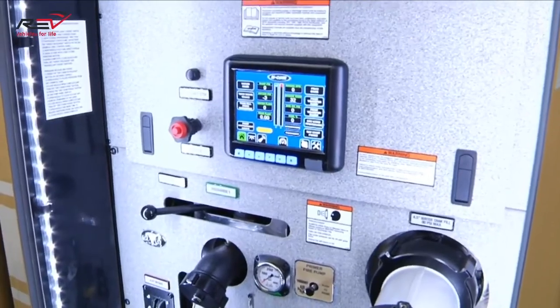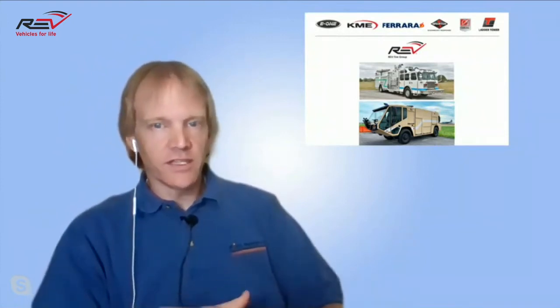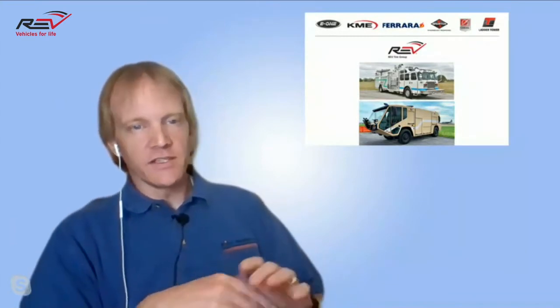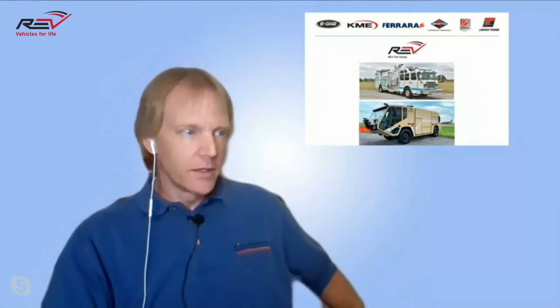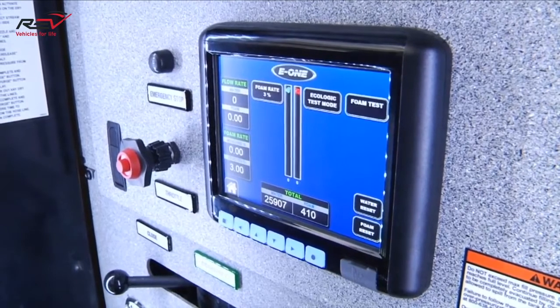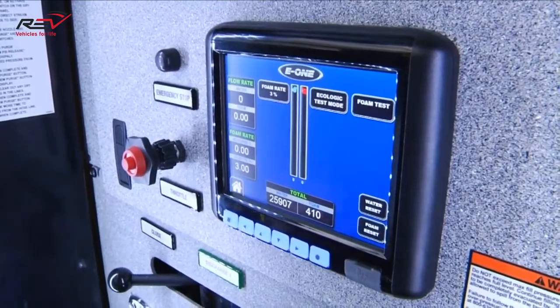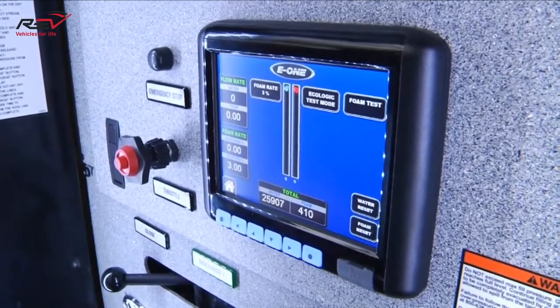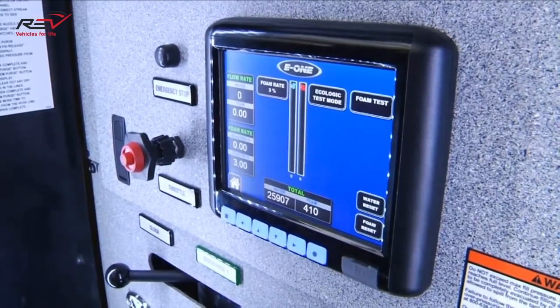We got a question from the audience, and I was also hoping you could touch more on the EcoLogic system. That's a particularly important system today — Jeff mentioned earlier there's a lot of not-always-good press right now for foam. The EcoLogic system really does address that. The EcoLogic is a patented foam testing system for E-ONE that allows you to test your foam system — instead of dispersing foam into the environment, it gives you the ability to test by dispersing water through the foam system to make sure you're hitting the percentages of foam expected out of each discharge point.